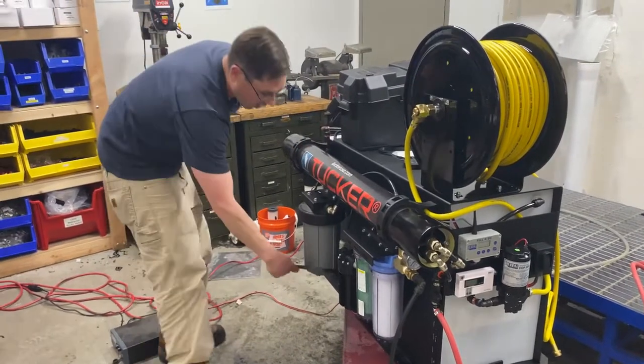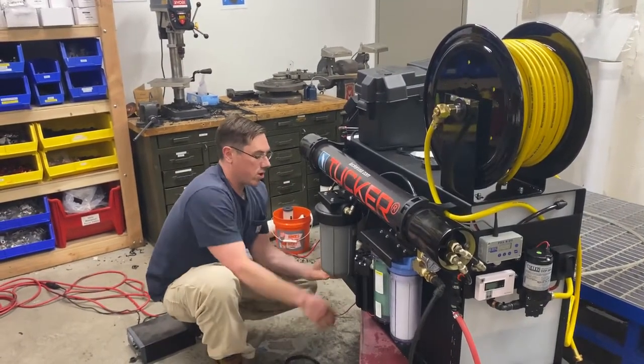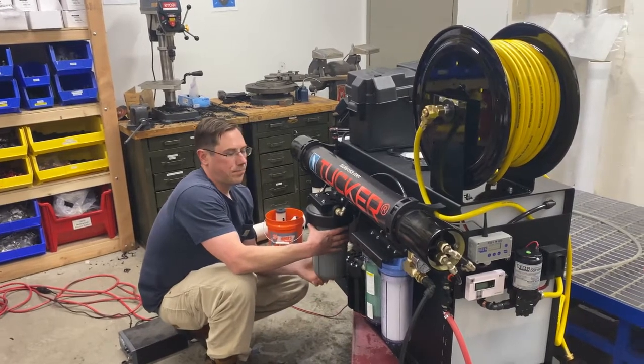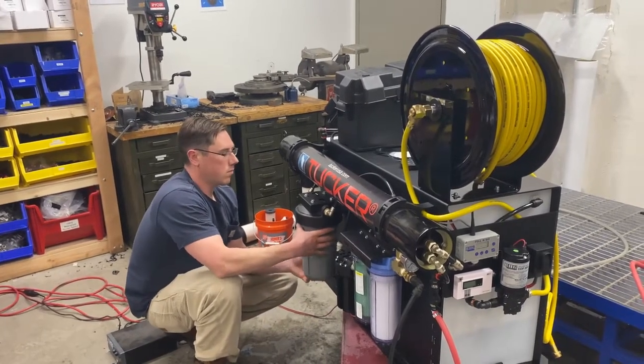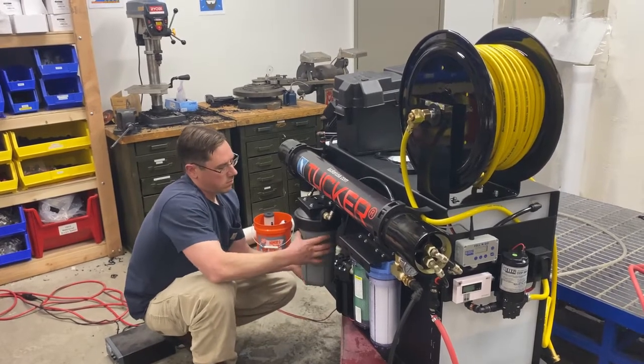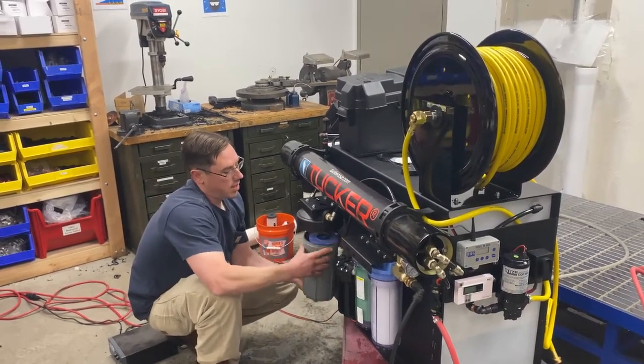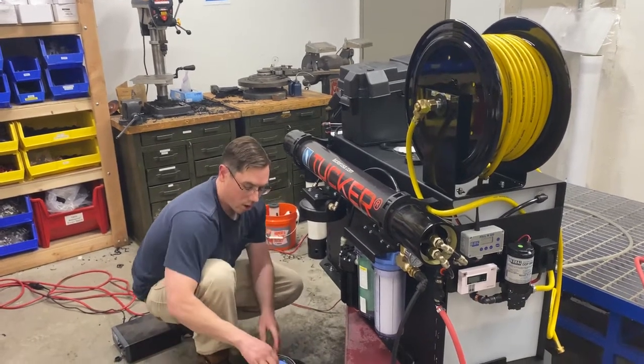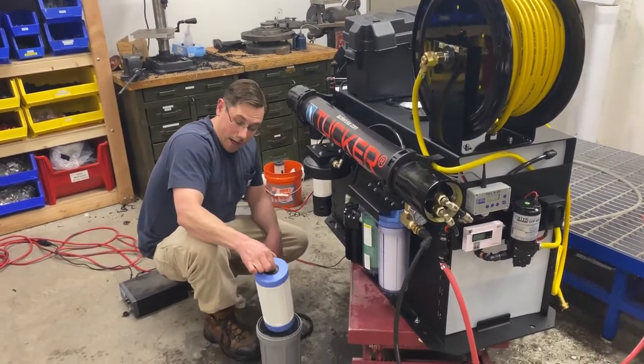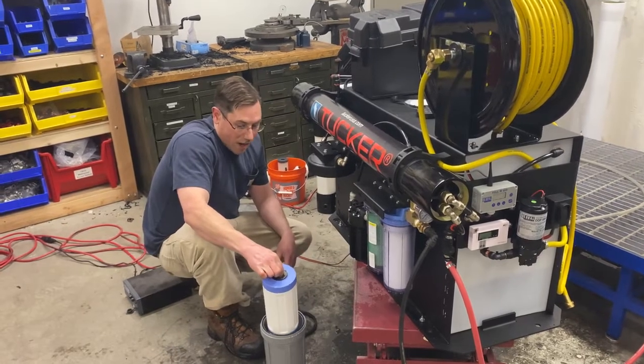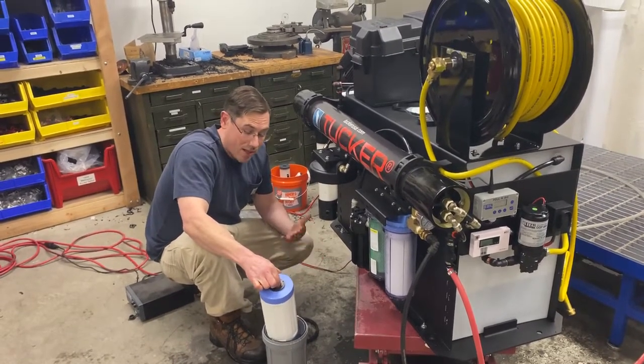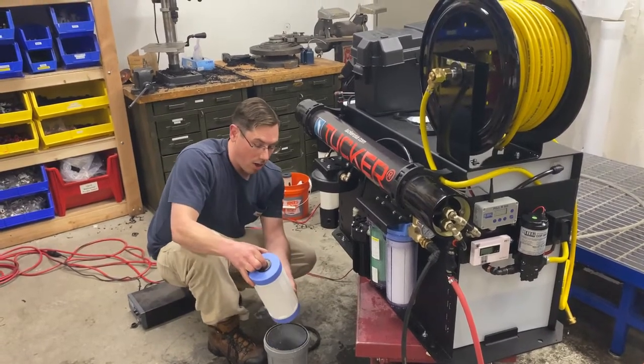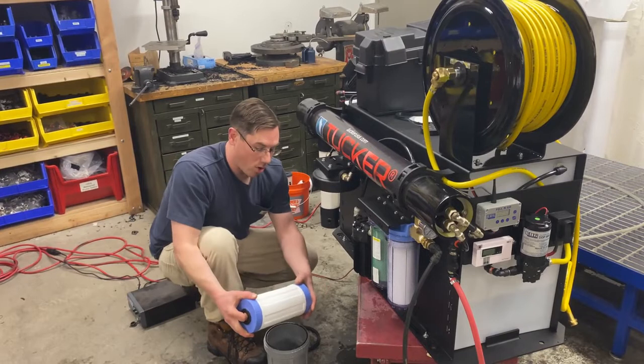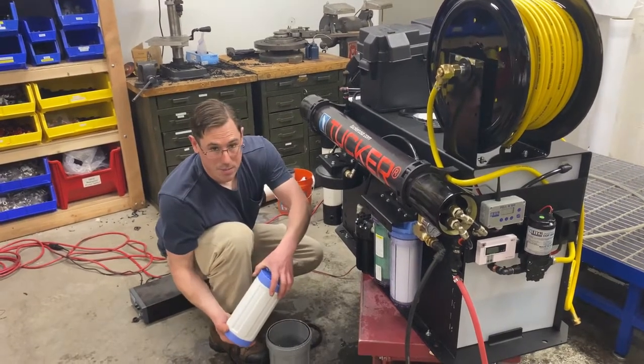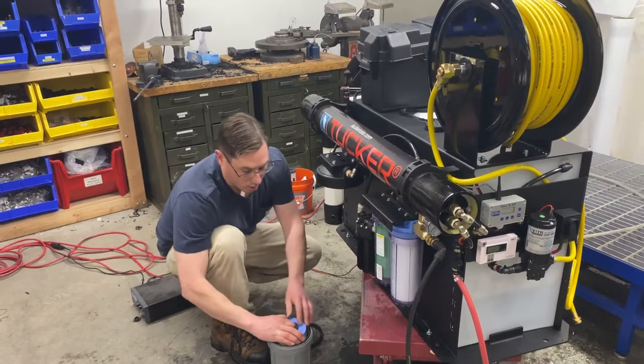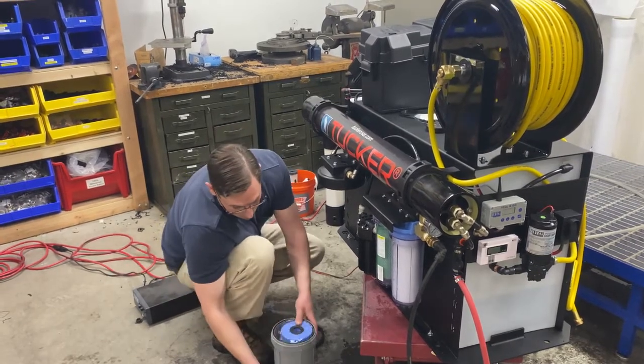And there's your 4.5-inch wrench to gain access to your DI filter. Inside is a serviceable DI cartridge. You can, again, have this on hand, ready to go. I wouldn't recommend that you buy any DI that you cannot use within 6 months. It does have a shelf life. You can get this entire cartridge, or you can open this cartridge from the back end and fill it with mixed bed DI resin. You can get virgin mixed bed resin directly from us.